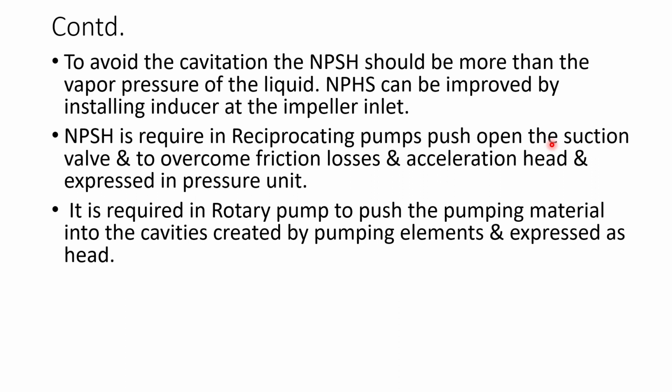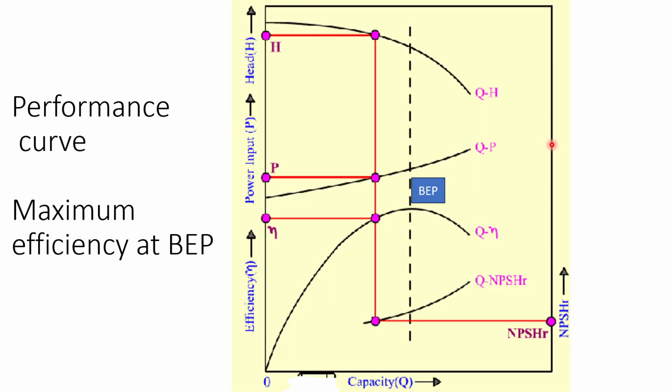NPSH is required in a reciprocating pump to push open the suction valve and to overcome friction losses and acceleration head, as expressed in pressure units. It is required in rotary pumps to push the pumped material into the cavities created by the pumping elements, and is expressed as head.